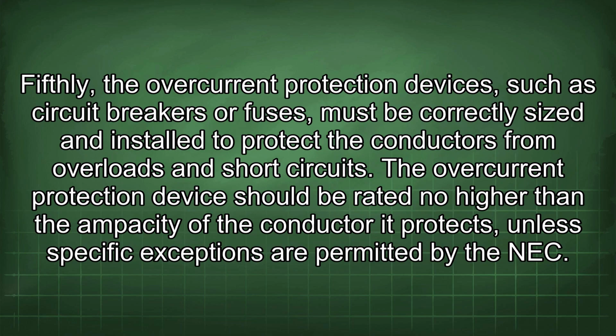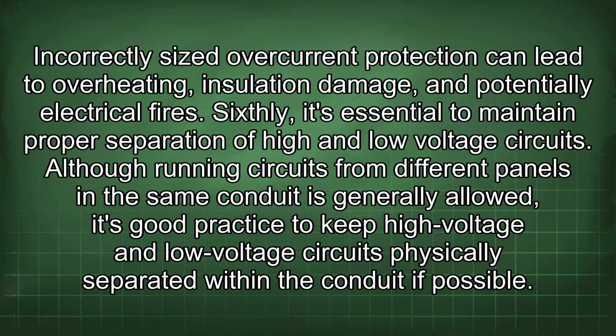Fifthly, the overcurrent protection devices, such as circuit breakers or fuses, must be correctly sized and installed to protect the conductors from overloads and short circuits. The overcurrent protection device should be rated no higher than the ampacity of the conductor it protects, unless specific exceptions are permitted by the NEC. Incorrectly sized overcurrent protection can lead to overheating, insulation damage, and potentially electrical fires.